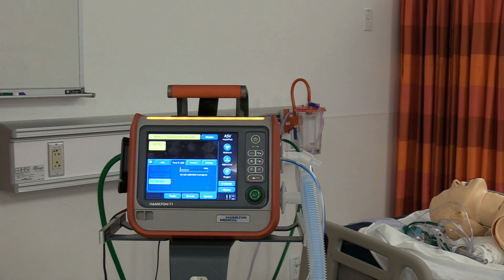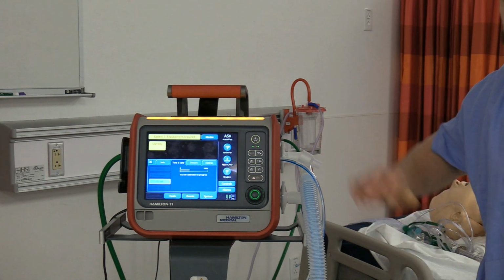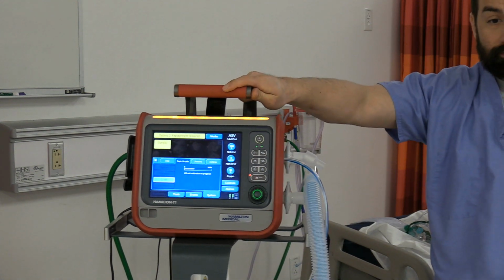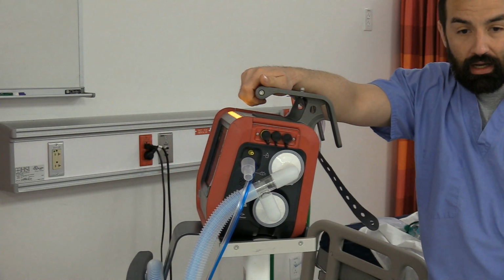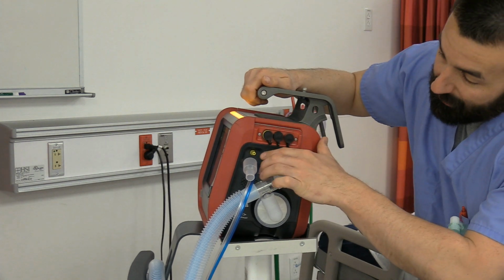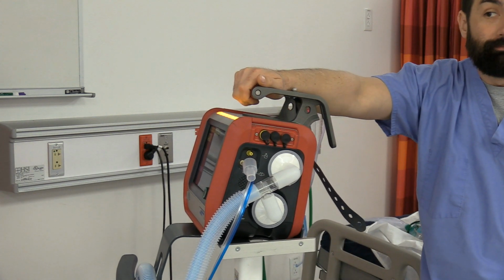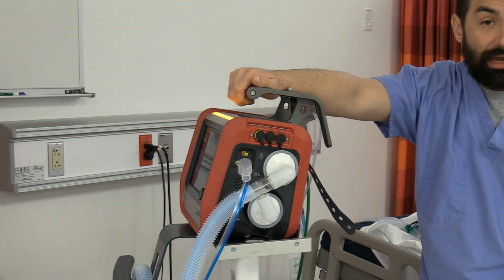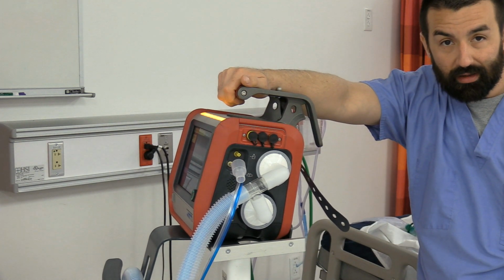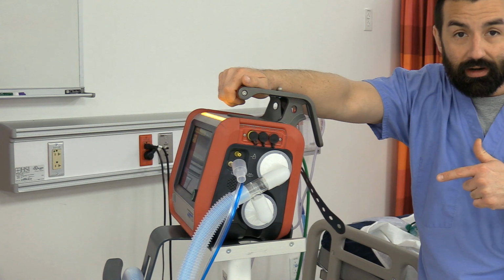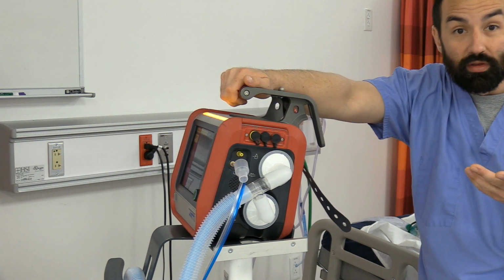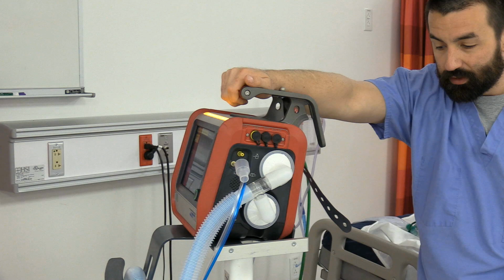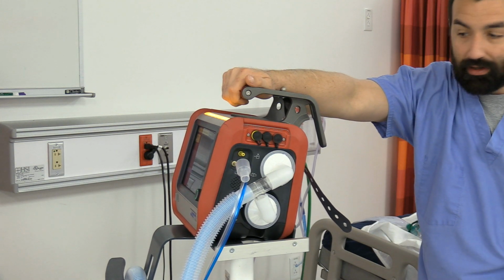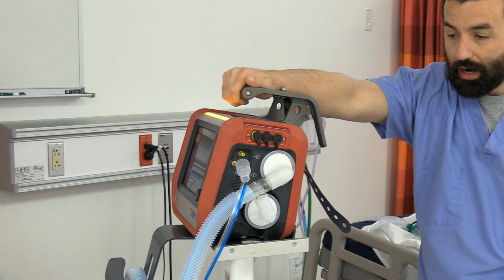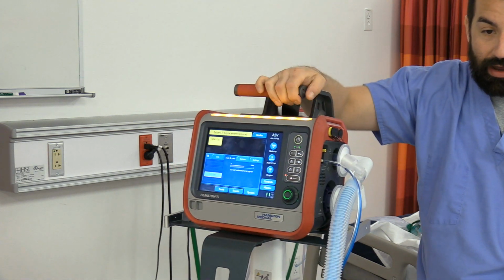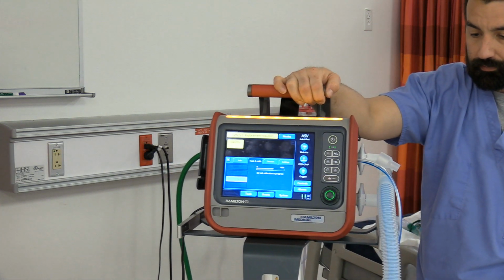You can see it takes a little bit of time to do this one, but it's not anything that you're necessarily having to do. While that's doing its thing, I'll show you the one port we did not talk about right here. It is an adapter for our standard jet neb. So if you're doing a valve T adapter and want to give nebulization, the benefit there is you can run it through the ventilator. You're not adding in any extra flow that the ventilator is getting from some unknown source, and you can deliver it by a more effective means without causing problems. I'll show you how to run that once we're up and running.